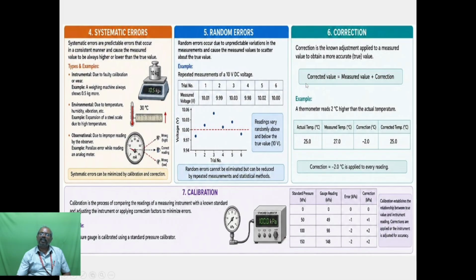Then correction. Correction is the known adjustment applied to a measured value to obtain a more accurate value. So corrected value equals measured value plus correction. Example for this correction: a thermometer reads 2 degree centigrade higher than the actual temperature. The actual temperature is 25 degrees Celsius. Measured temperature is 27 degrees. Correction is minus 2.0. So corrected temperature is 25. Then calibration. Calibration is the process of comparing the readings of a measuring instrument with a known standard and adjusting the instrument or applying correction factors to minimize errors.